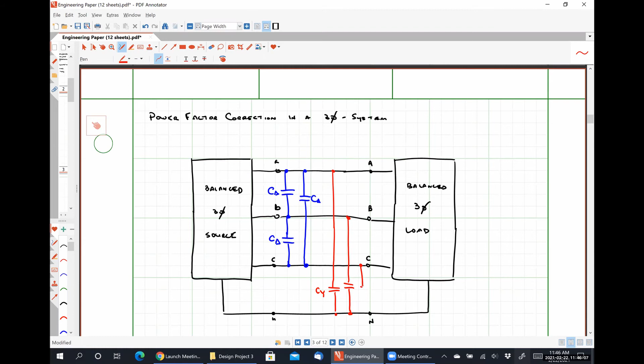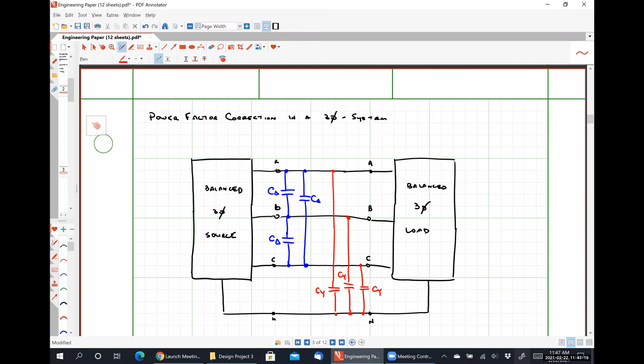Typically speaking, you'll use a delta-connected capacitor bank because the size of the capacitors will be smaller and therefore cheaper, but they also have to be rated for a larger voltage. So there are trade-offs. There may be some special situations where you would use a Y-connected capacitor bank, because getting capacitors rated for that larger voltage may be prohibitively expensive or something like that. You do have two options technically, but in practice, the overwhelming majority of the time, you would use a three-phase delta capacitor bank.